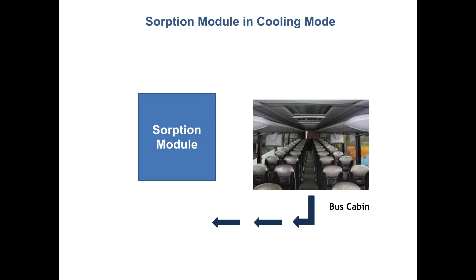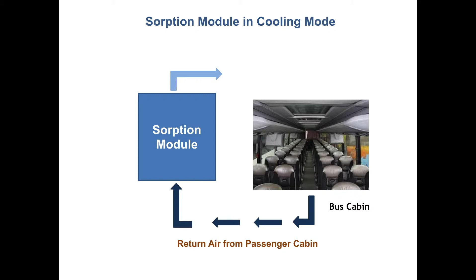This charged sorption module has the capacity to provide cooling in the cooling mode of operation. In cooling mode, return air from the bus passenger cabin is passed over the sorption module, which was in regeneration mode in the previous cycle. As the return air passes over the sorption module, it starts discharging, and in this process cooling of the return air is achieved. This cool air is supplied to the vehicle air conditioning ducts as supply air.